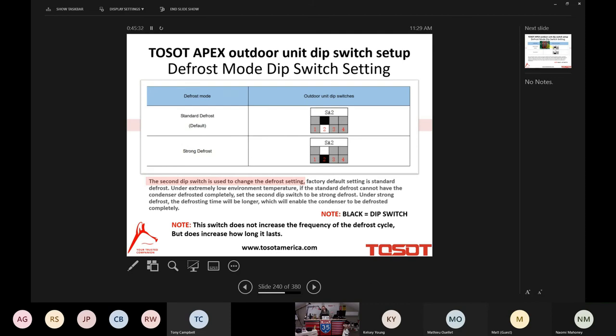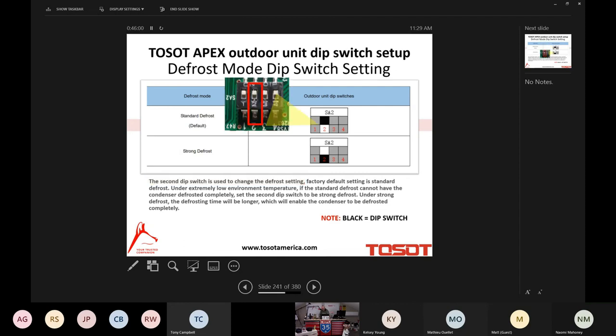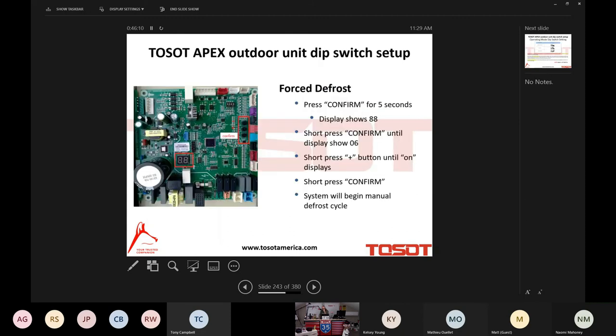I say this to you, having said that, wait, out of the box, don't immediately start moving from the factory defaults, in this case, the standard defrost. If you need it, that can be done after the fact. But I strongly suggest keeping it in the standard defrost until further notice, right? Until you decide, or until your installer, I should say, realizes that it needs that additional time. And that, again, is all done at dip switch 2 of the outdoor unit. So for standard defrost, it's in the up. For strong defrost, it's in the down position.